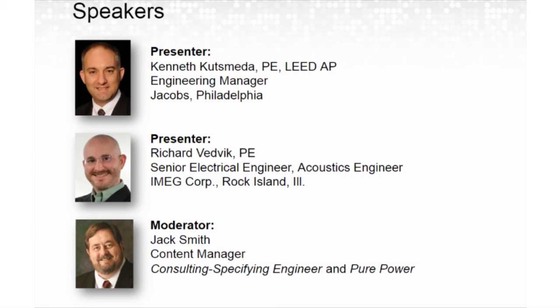But certainly a comparative graph to say here's all the different combinations you could possibly achieve is something you'd want to communicate with your transformer vendor. We've talked about a couple different types, right? We've talked about TP1 and CSL3 and NEMA Premium. There's also ultra efficient, I say ultra in air quotes, transformers that have even better efficiencies. They're going to make an advantage by trying to minimize losses, and each one of those manufacturers does it in their own kind of proprietary way.